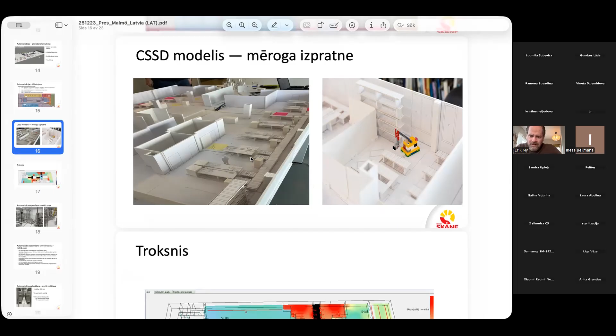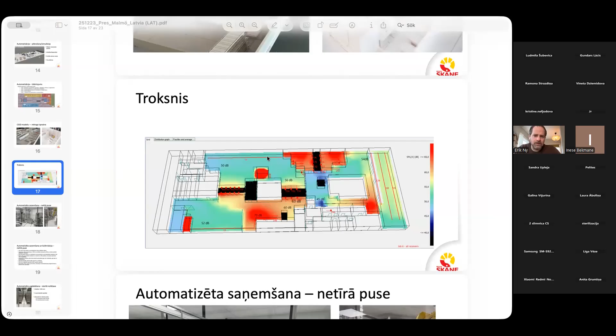Our main packing robot is over here. You see that's a red spot. What we didn't take into account is the administrative area, and the lunchroom is here. So when that robot is operating, you can hear it all through this section. So that's something to consider. Otherwise, we have tried to seal off the noise so that it doesn't travel to the areas where people work. 50 decibels, 52 decibels, those numbers are practically dead silent. So it's a good environment to work at the main manual workstations, at the washing and at the packing.